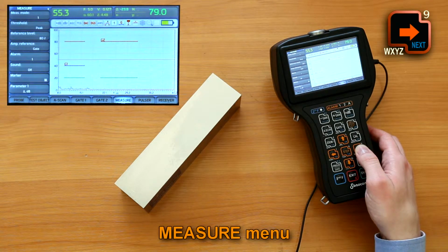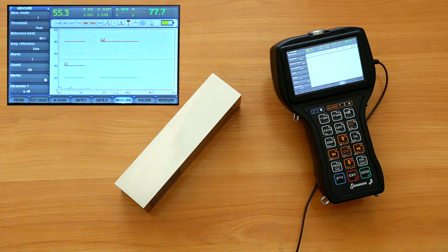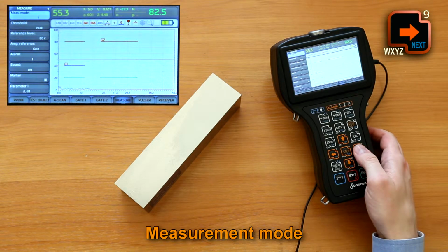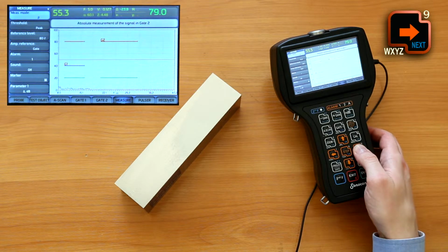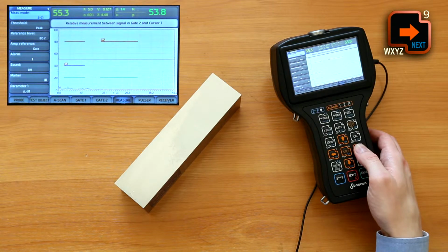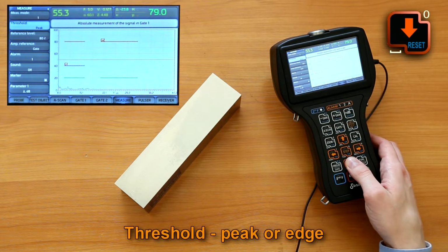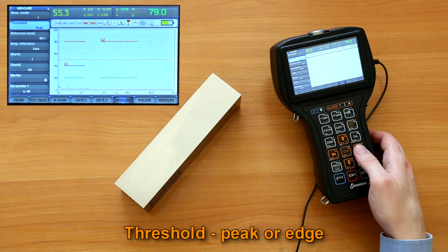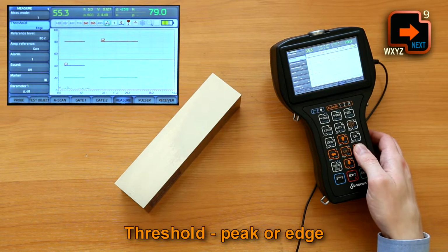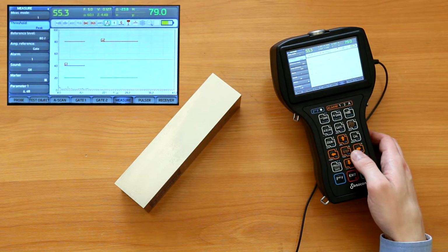In Measure menu, we can find settings related to the indications parameters measurement. Measurement mode lists all measurement tools, gates and cursors, and their combinations. Threshold indicates which points of the signal to take as a reference, its peak or edge.